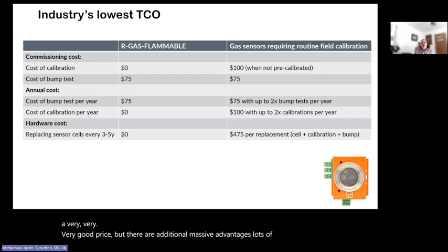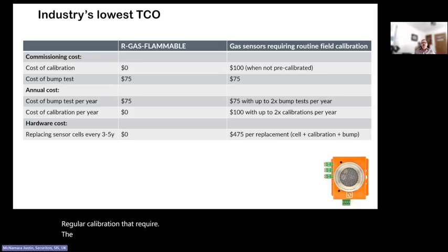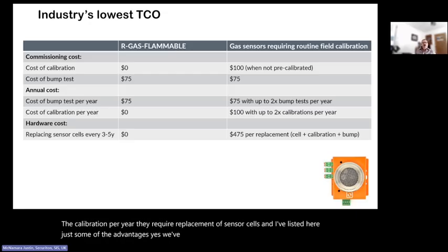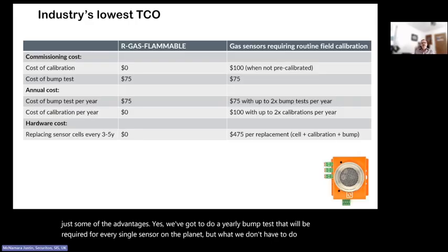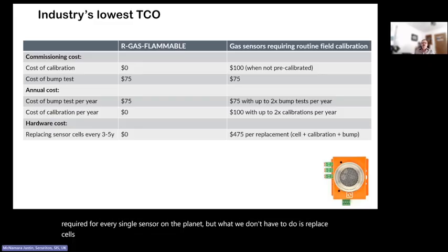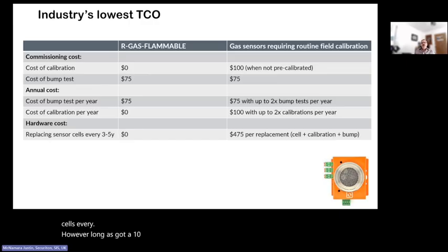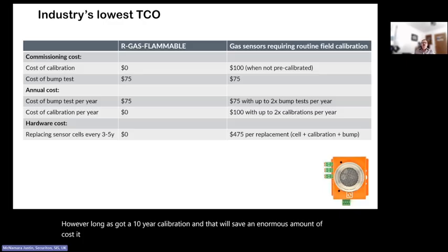Lots of other gas sensors require regular calibration. They require calibration per year. They require replacement of sensor cells. And I've listed here just some of the advantages. Yes, we've got to do a yearly bump test. That will be required for every single sensor on the planet. But what we don't have to do is replace cells every however long. It's got a 10-year calibration, and that will save an enormous amount of cost. We're also not having to do calibrations every year, and again, it's a cost saving.